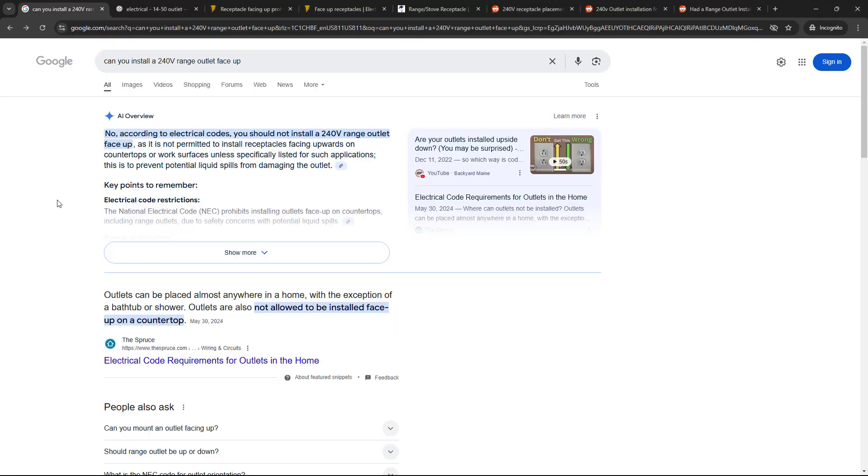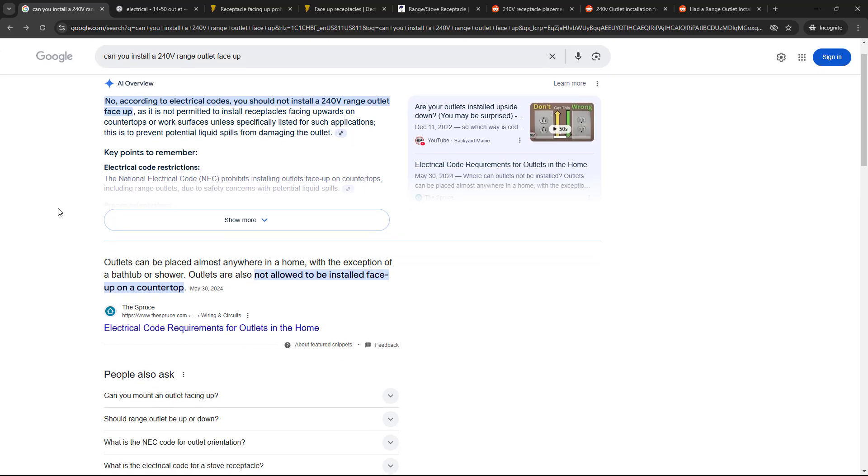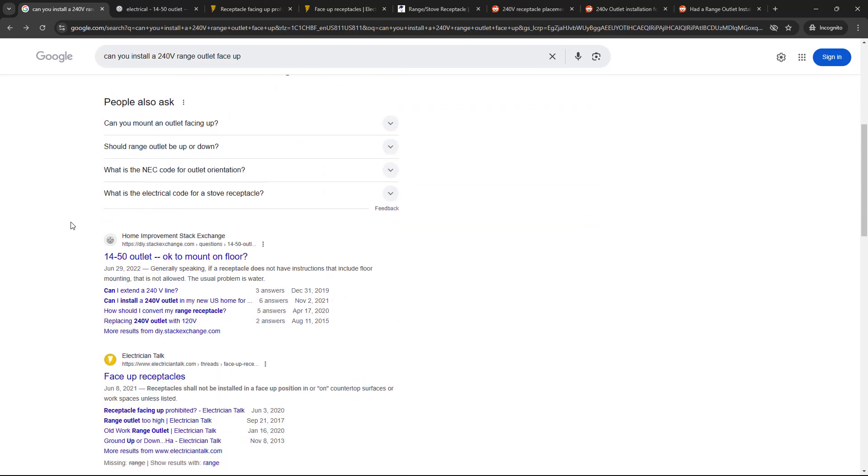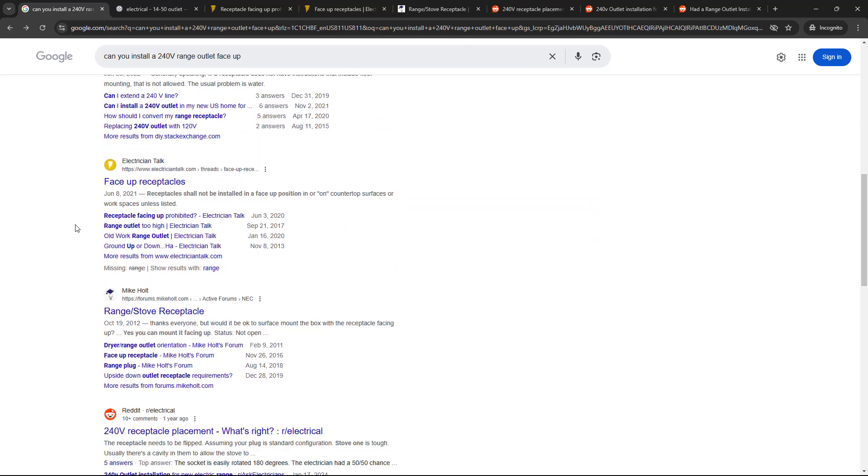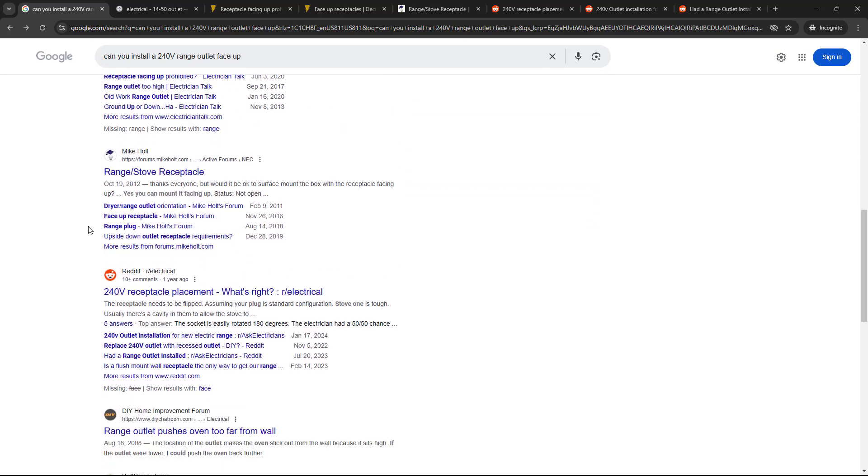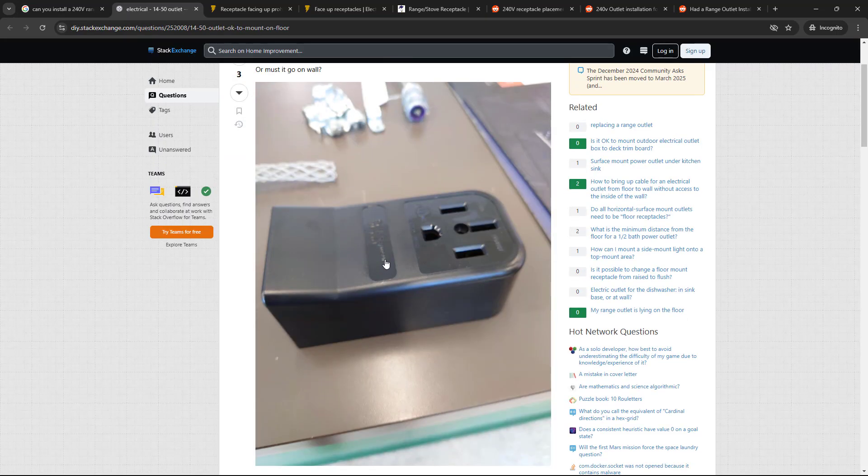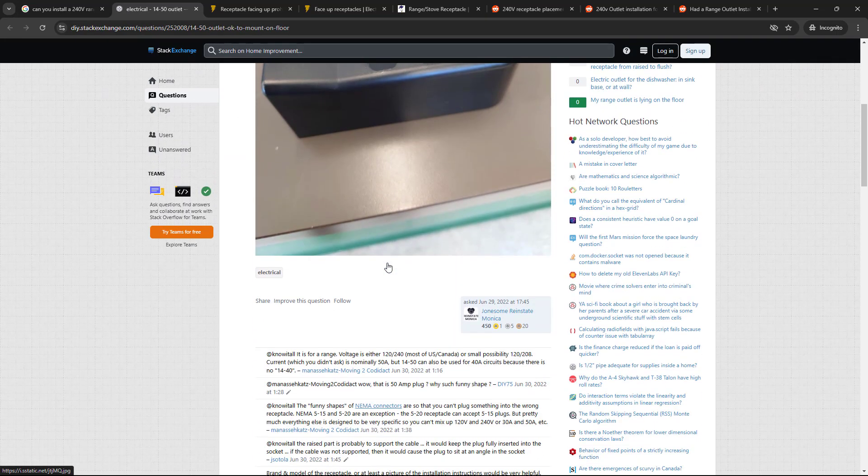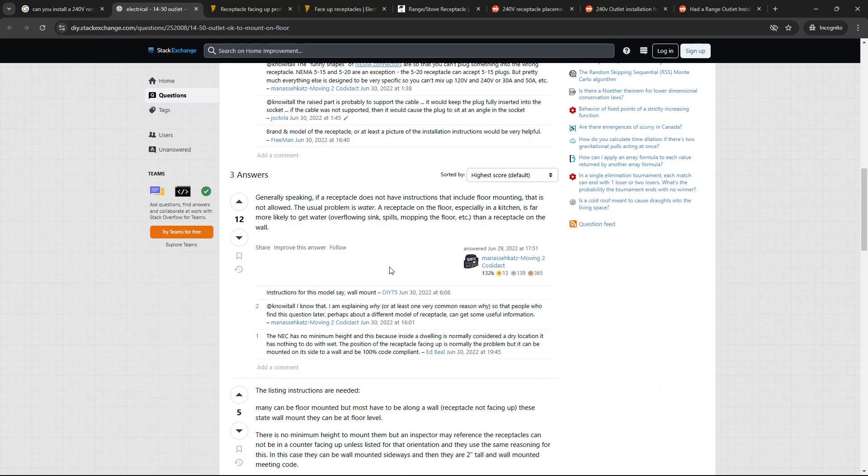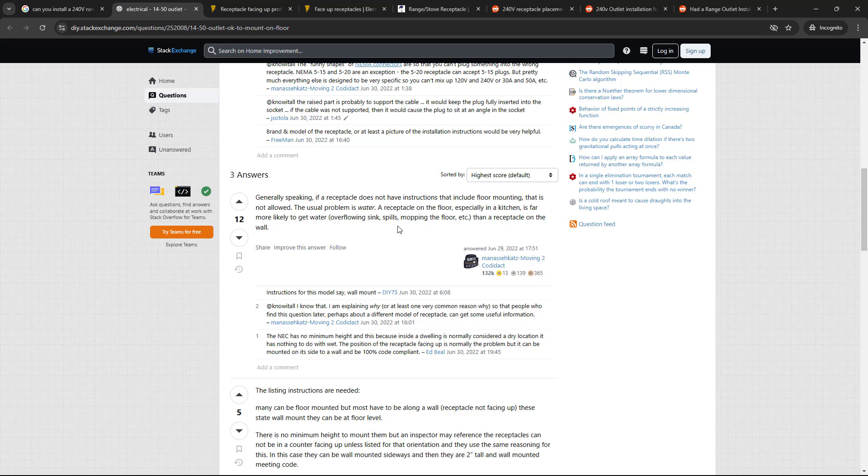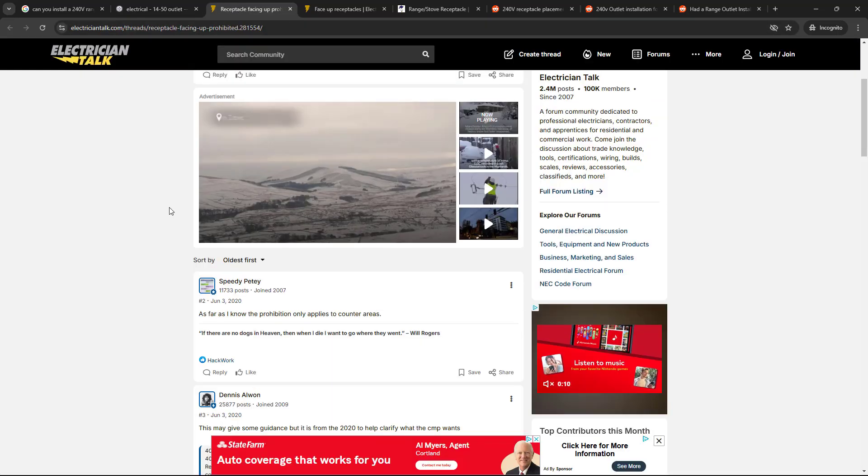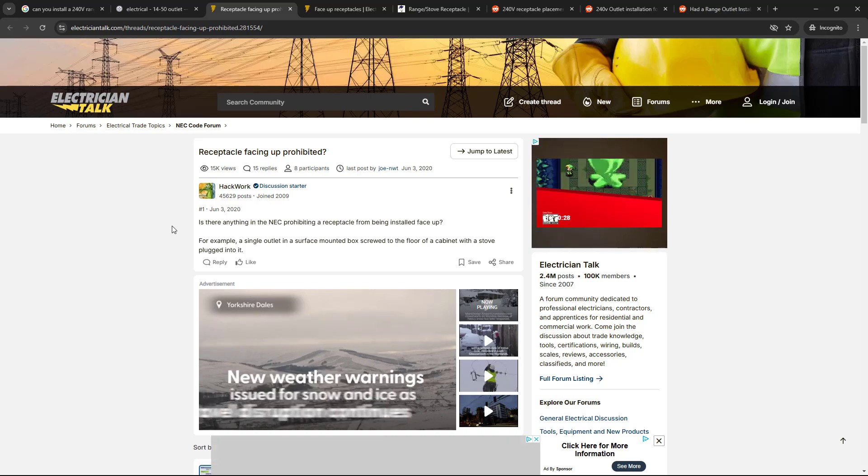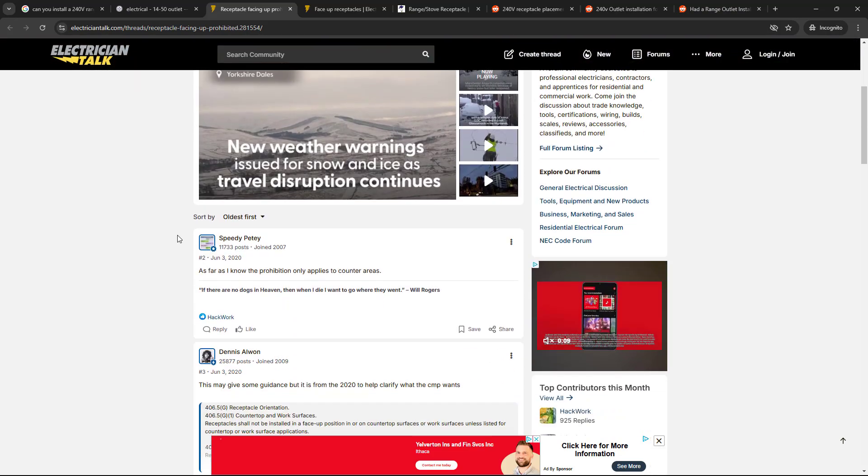And if you Google this question, you will find a ton of forum threads where people are asking the same thing. And there are answers ranging from saying no, it's not up to code at all, to the National Electrical Code actually only bans face up outlets on counters where they are more likely to encounter spills. So technically, it's okay to do this on the floor.